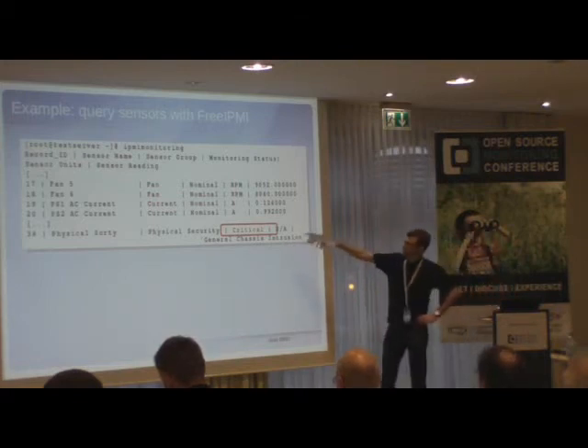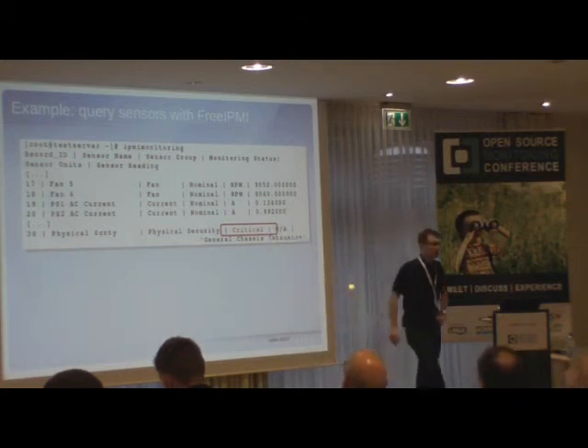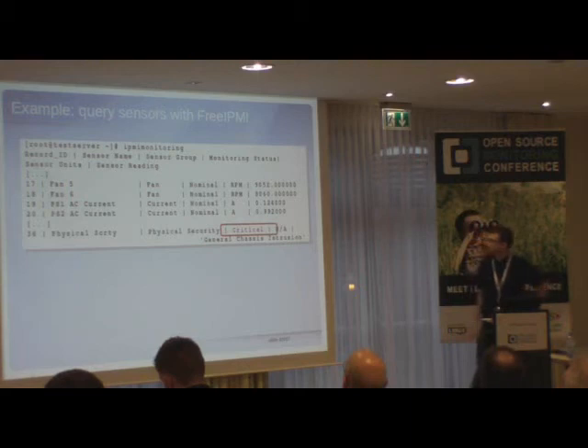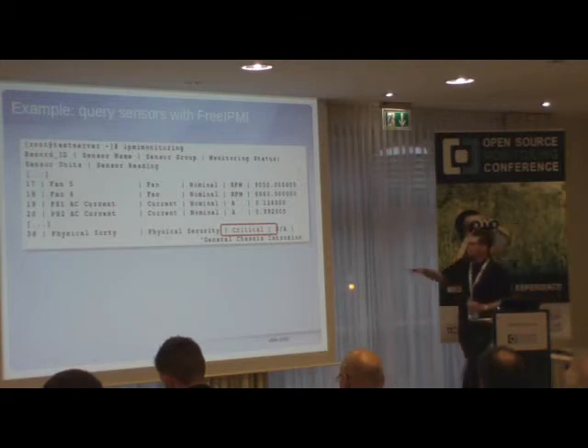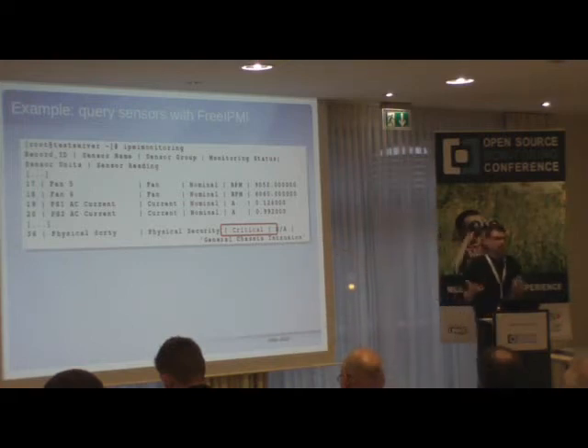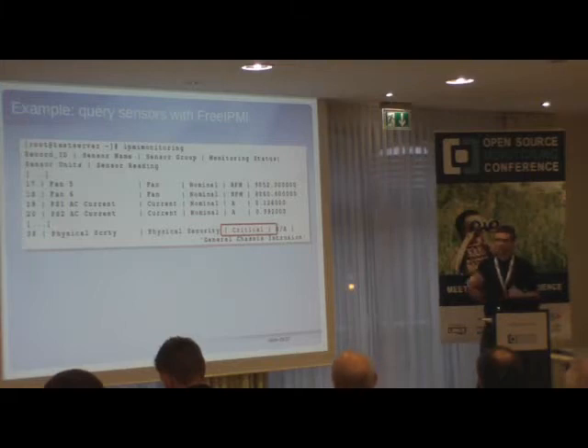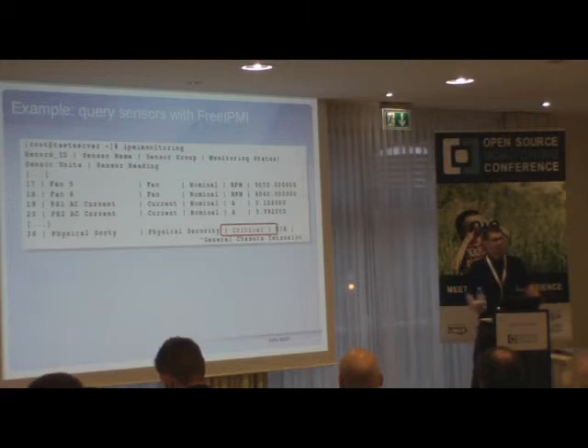For those discrete sensors, one might think that yes/no information could have a different meaning for different people. For example, when you have redundant power supplies — say a 4U server with three power supplies — you might say one power supply is enough to run the server, or you might want a warning when only two are running. Should that be a warning or critical? This can be configured in the FreeIPMI configuration.